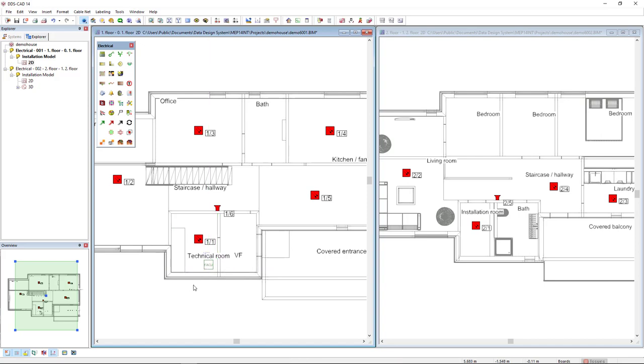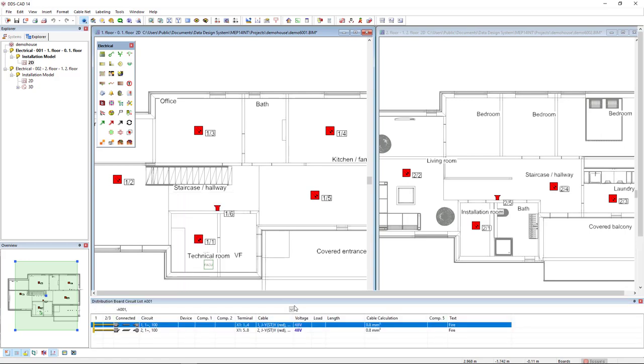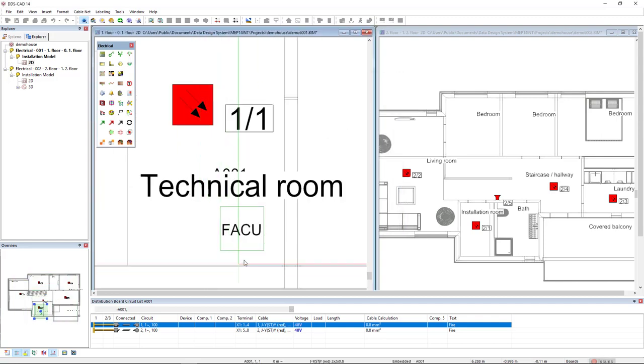Now I will start drawing the cable and connect to the objects. To do so, I will come to the bottom of the interface, right mouse click to select the option distribution board circuit list, so that I can directly see the circuits while I have available also the models in the interface. I will select the first circuit and select the option draw cable. A fire warning installation cable is automatically selected.